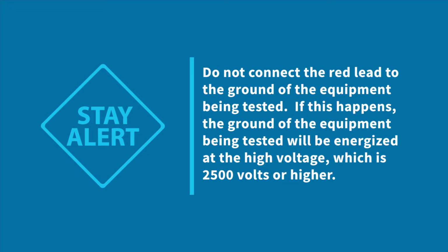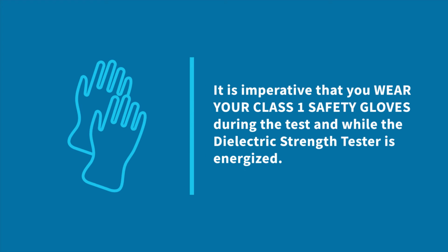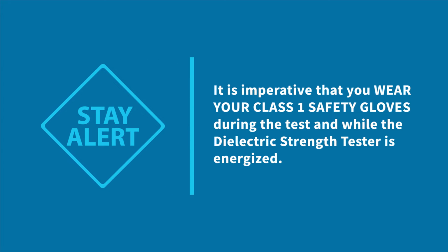Do not connect the red lead to the ground of the equipment being tested. If this happens, the ground of the equipment being tested will be energized at a high voltage, which is 2,500 volts or higher. It is imperative that you wear your Class 1 safety gloves during the test and while the dielectric strength tester is energized. Never handle the high voltage test leads when they are live without the use of Class 1 safety gloves. Make sure to stay alert at all times during the test.